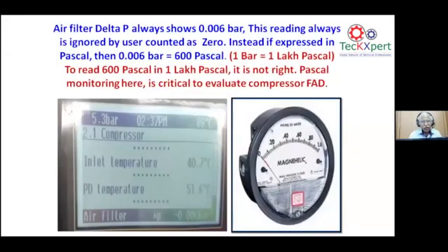Next comes the gray area, which is happening throughout India and throughout the world. I came across this in many of our energy audits. We are measuring less than 1% of the Pascal on the air intake filter. This is from one OEM and this is from the next OEM. On the compressor air intake filter, the differential is around 600 Pascal. If it is mentioned as 600 Pascal, the user will take immediate steps and correct it. If it is shown as only 0.006 bar, he ignores it. 1 bar is 1 lakh Pascal, so it is less than 1% and not readable.